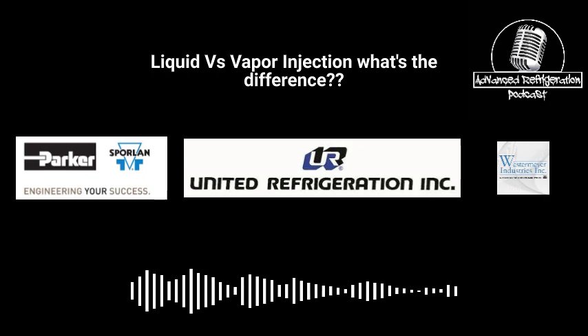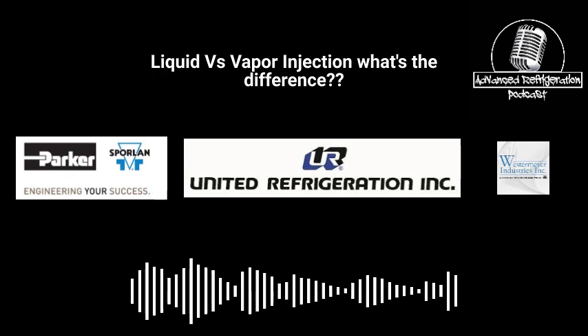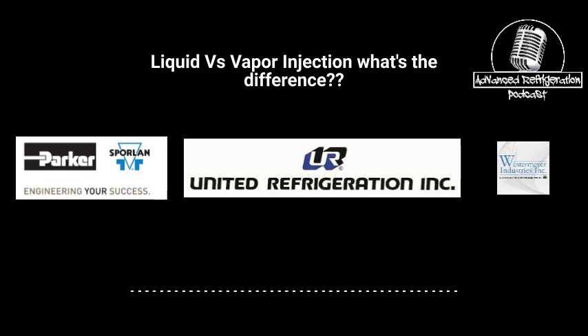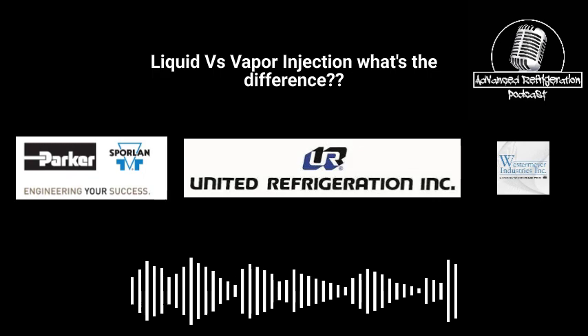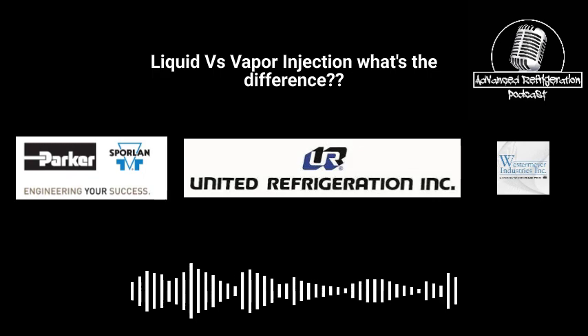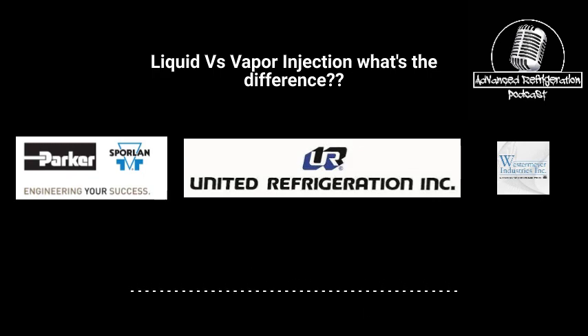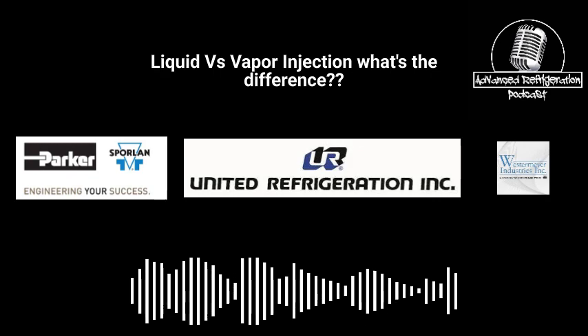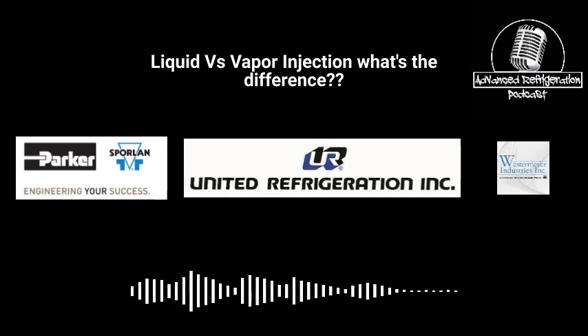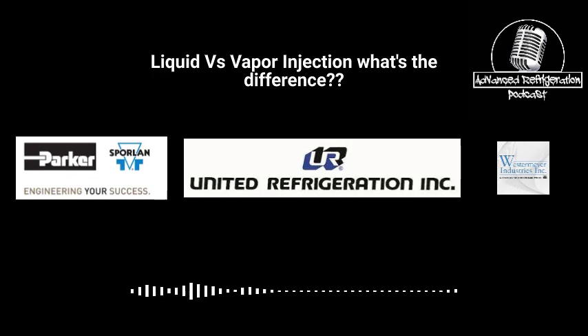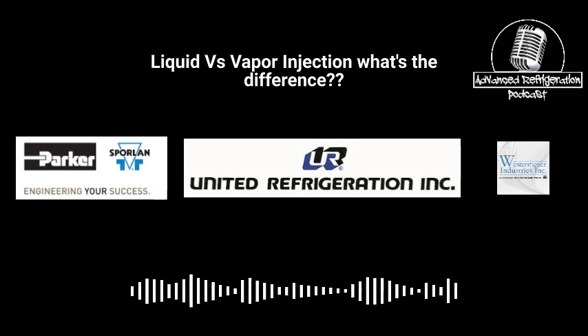Most of the time, manufacturers will size these valves for a 35-degree superheated suction. So if you're dealing with, let's just say, -20 saturated, they're expecting that suction coming back when they design that valve to be running at like +15. If you do run outside of those parameters, higher than what the suction is supposed to be, that valve will not be big enough and not adequately cool that compressor.